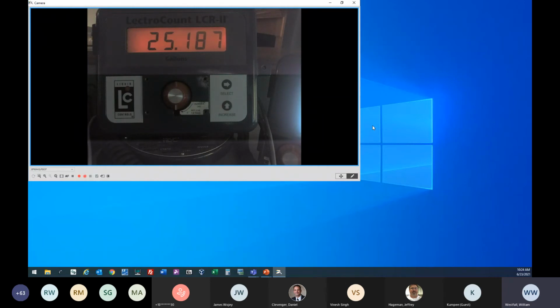What's going to happen here is, in this case, your far left-hand digit is going to start to flash. This is indicating that it's waiting for you to enter in what's in your prover. So let's say we've got 25 gallons exactly in our prover, so we want to put 25 gallons in there. To change the numbers, all you have to do is hit the increase key to cycle through the numbers until you get what you want. In this case, we're going to put 25. So 0, we're going to leave the 2 alone, we're going to leave the 5 alone, and then we're going to change this 187 to 0. So we just keep going all the way around until we get to 0. And then once we get to 8, turn that one to 0.